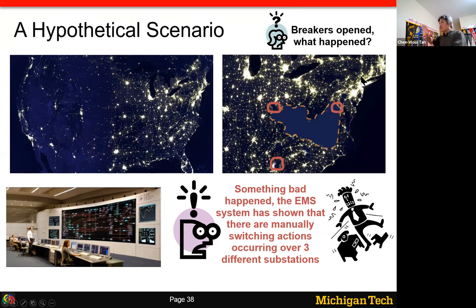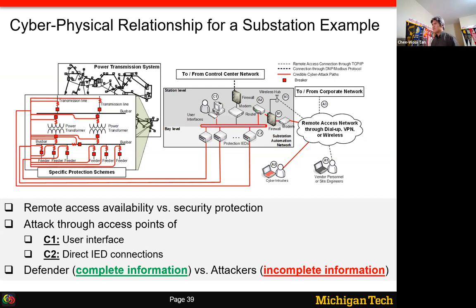So the physics part doesn't change, but the initial event can change due to the cyber attack. The cyber-physical system correlation is that regular maintenance—logging into the cyber system across hundreds of substations—means an attacker can log in, plan things out, and discover more from the local console, which has complete access to the switchgear in that substation. Thankfully, if an attacker compromises only one substation, they only control that substation, not all substations in the control area.